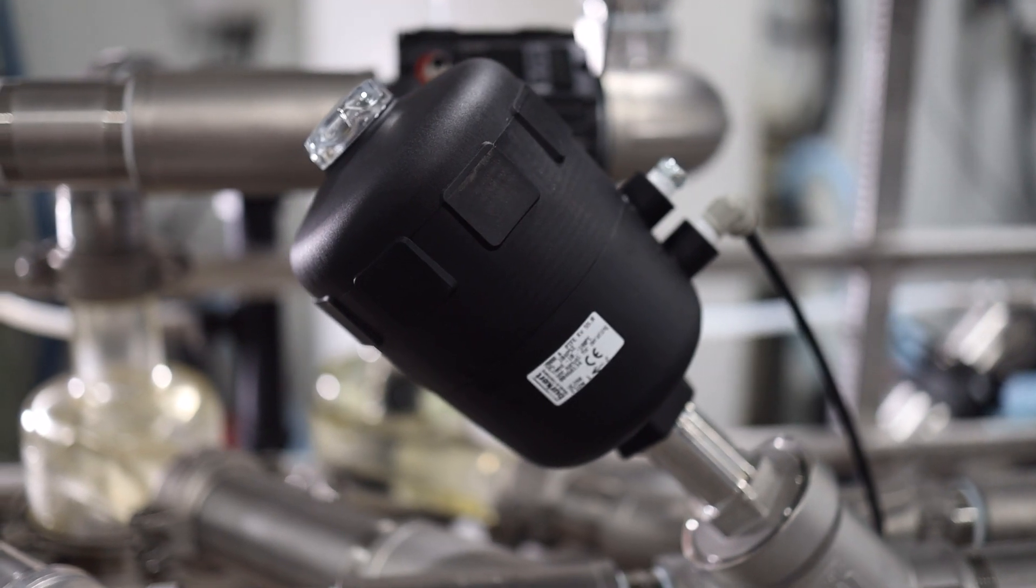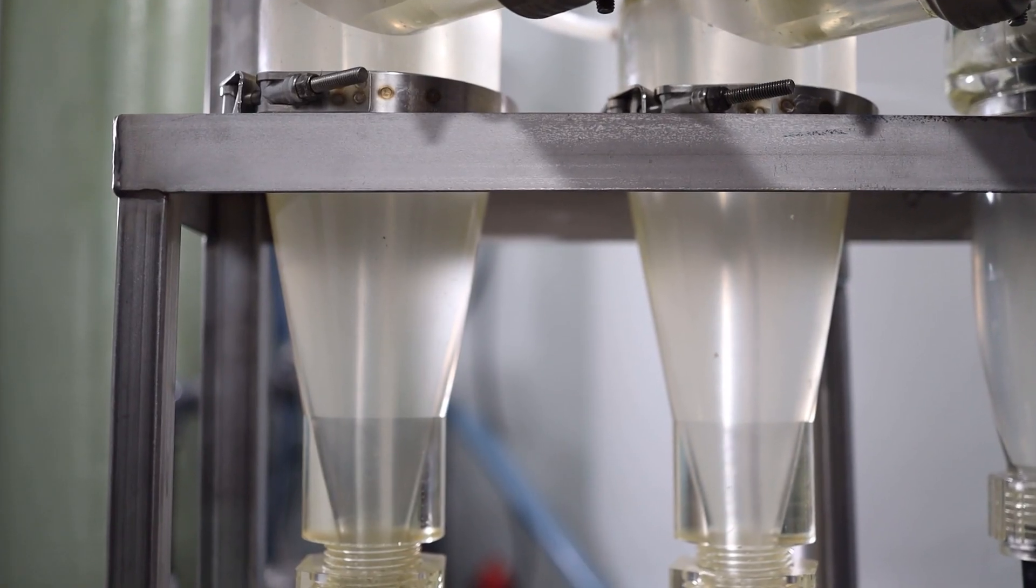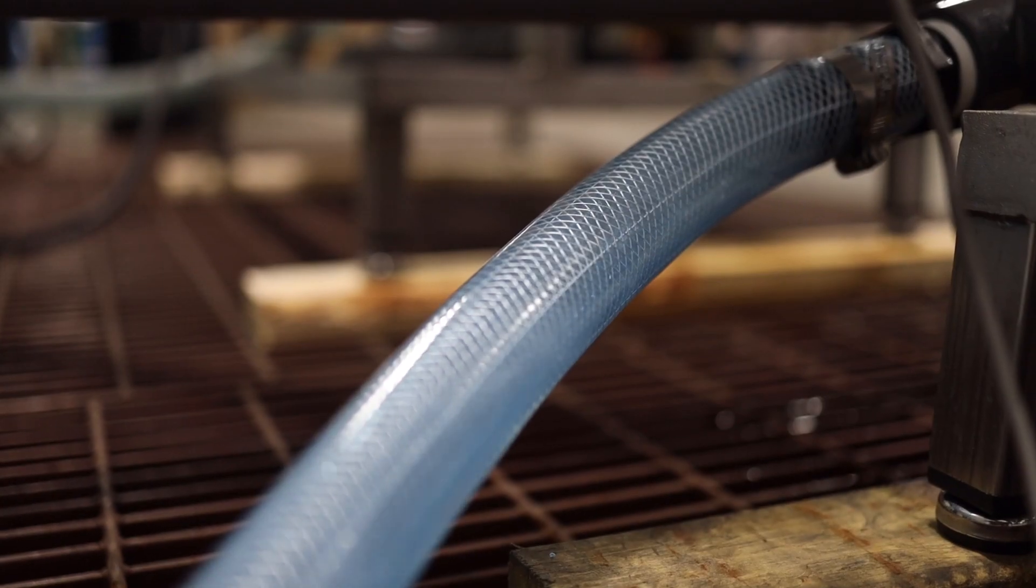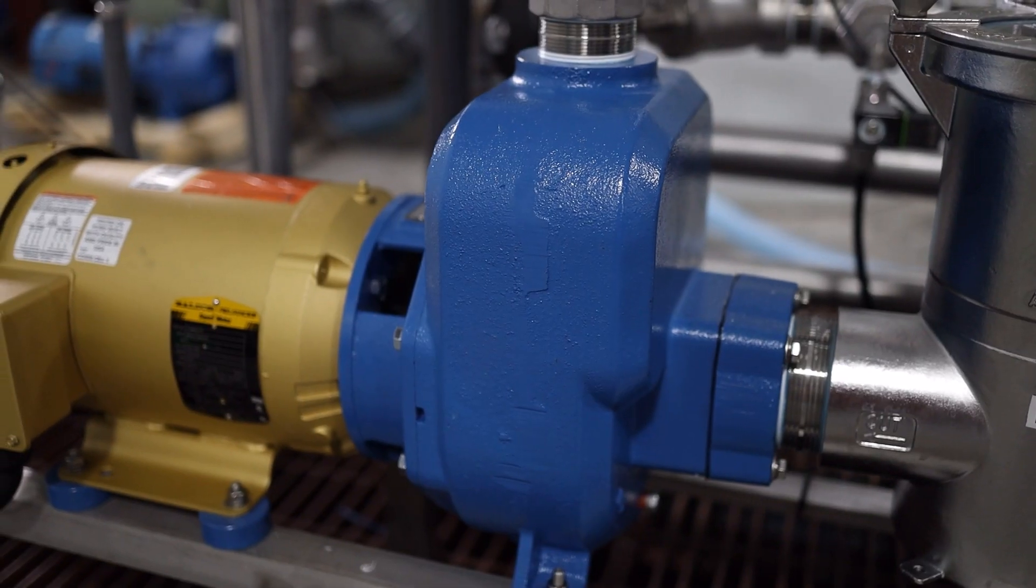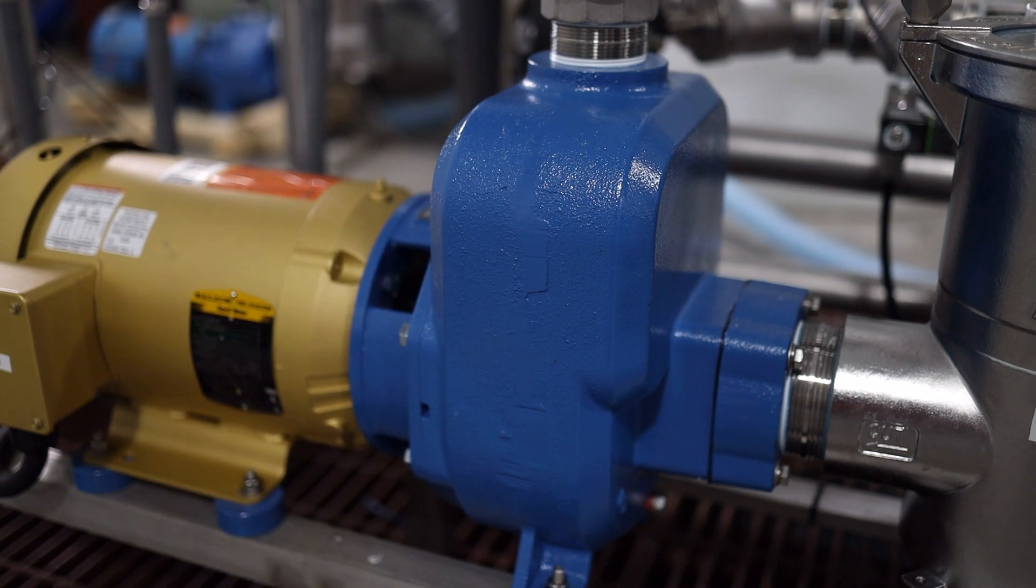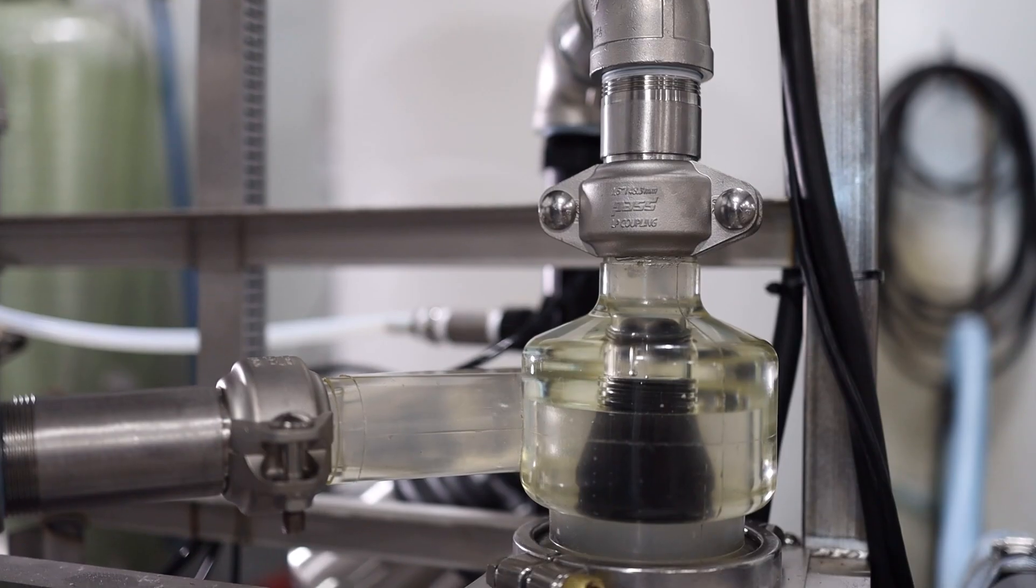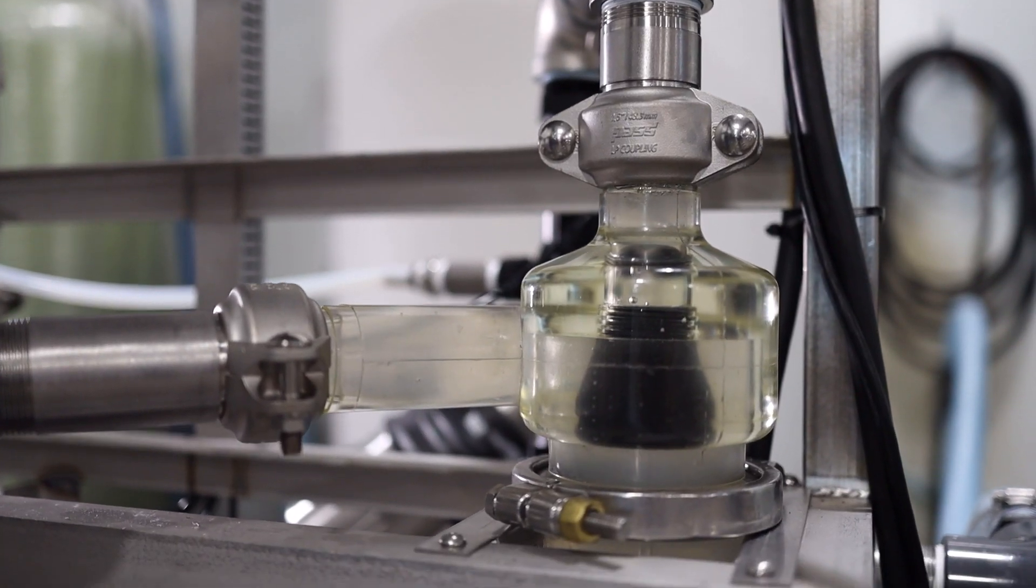The primary valve opens to deliver water to the process cyclones. Each is engineered to pass 50 gallons of water per minute. The unit is controlled by a pressure transducer to manage the pressure going into the cyclones and regulated pressure going to the car wash.